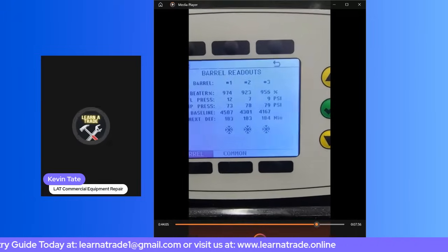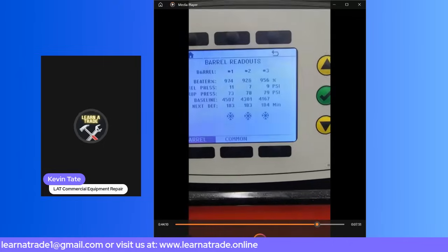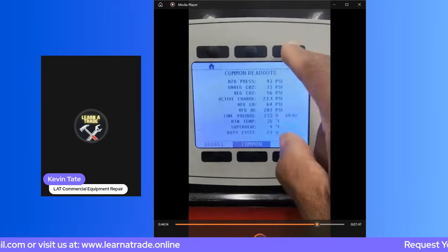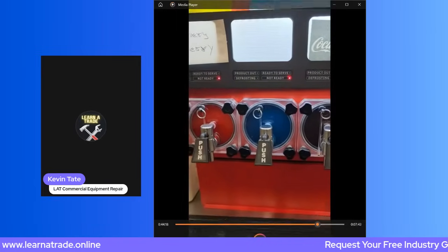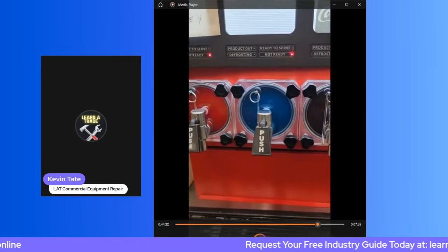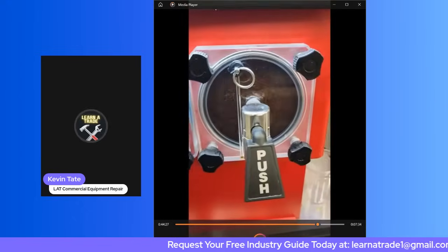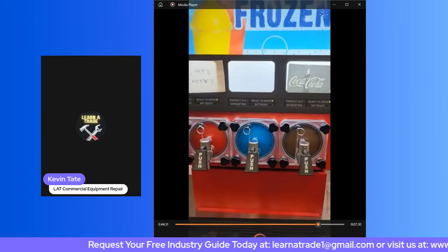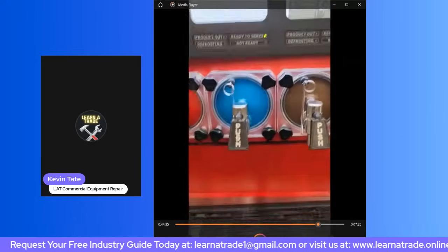So this is a great tool to use, to go to your readouts while the machine is running, because then you can see what your pressures are, what your temperatures are, and that will tell you a whole lot as you're troubleshooting the machine.